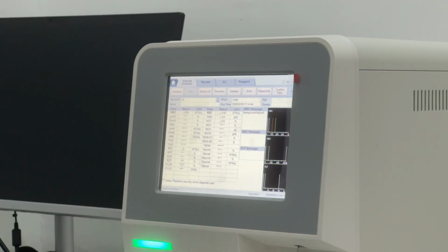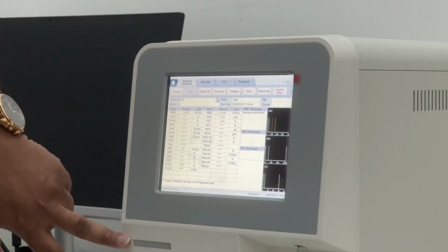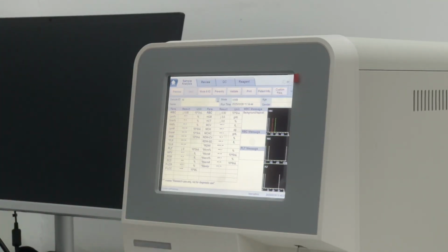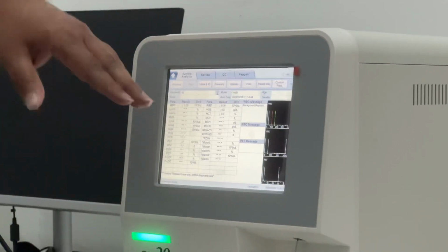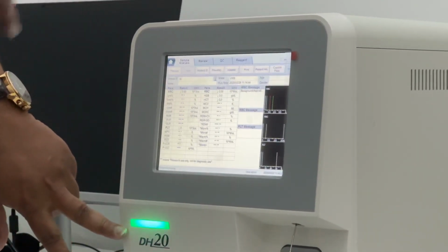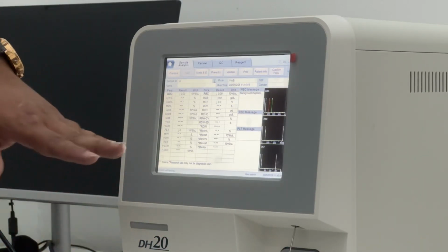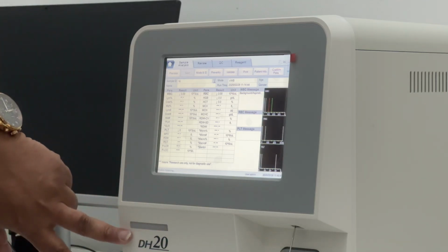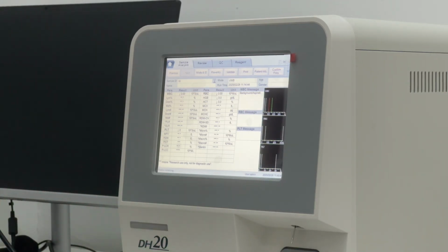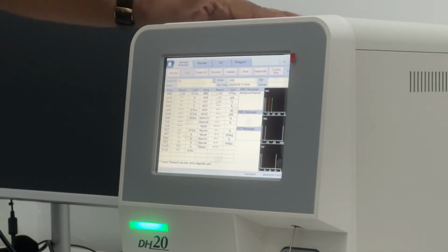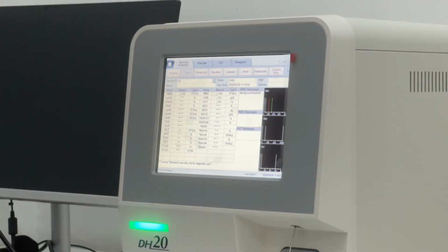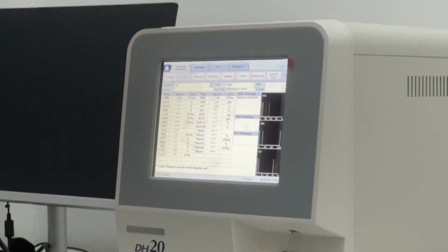Like what I said just now, red color is for error. Of course, this is a workable machine, so we can't see any error here. The next one is the blinking green color. Green blinking means it's analyzing. Even though it's doing self-testing, checking everything, the machine is doing some testing, that's why it's showing the blinking green. Once done, it will show a permanent green color over here. That means it's ready for the next sample. So we will just wait about 4 to 5 minutes for the machine to be ready to run the sample. While waiting, I want to explain another thing: we have a thermal paper here. Our thermal paper is something like this. When the printout comes out, it will come out like this.